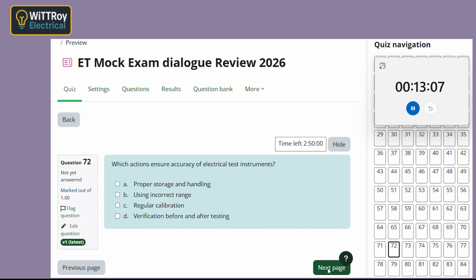Question 72. Which actions ensure accuracy of electrical test instruments? Calibration and checking before and after? Yeah, that's right. Instruments can drift over time or get damaged. So if we don't check, we might trust a wrong reading. Exactly. So you verify before using it and again after just to be sure it hasn't failed during testing. And storing it properly helps too. Yep, looking after your tools is part of getting reliable results.